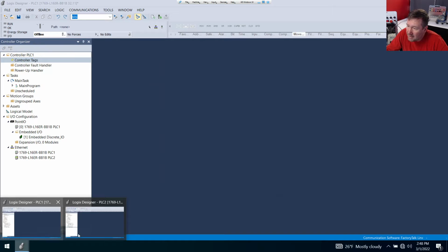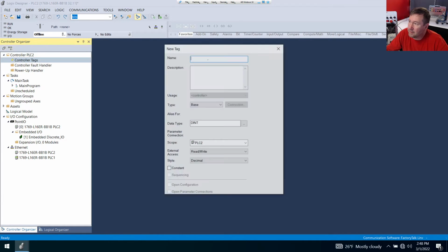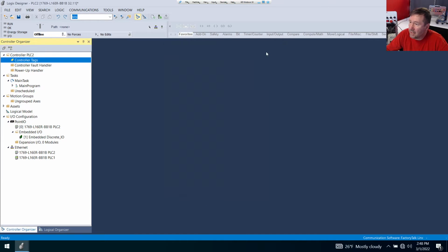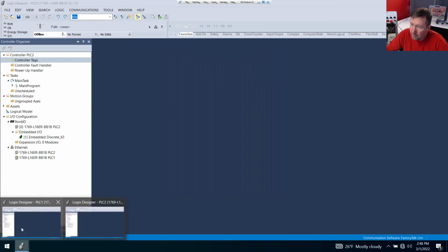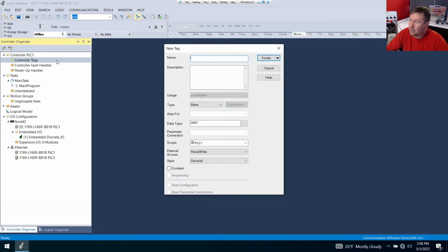And then I'm going to go to my right Studio 5000 and do the same thing. Right click, New Tag, 2 PLC. And this one's also going to be a produced tag, Create. And then go back to your left one. And we're going to right-click Controller Tags, New Tag. And this time it's going to be from PLC. And from would be a consume. That's something we're consuming from something else.